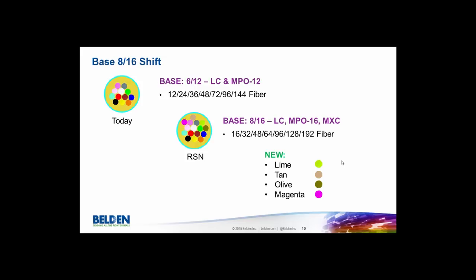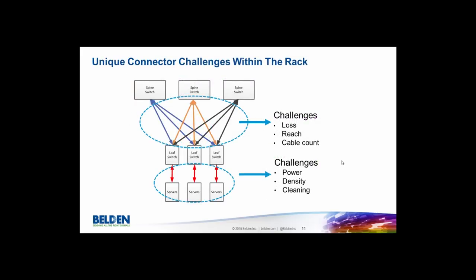What's coming is called the base-8/16 shift. Today everything is based on 6 and 12, but we're moving to 8 and 16 in the next couple of years. You'll start to see different fiber counts in cables, and four new colors introduced inside cables to cover those extra fibers — fibers 13, 14, 15, and 16. Lime, tan, olive, and magenta will be introduced as standard colors to help align this new connectivity paradigm.